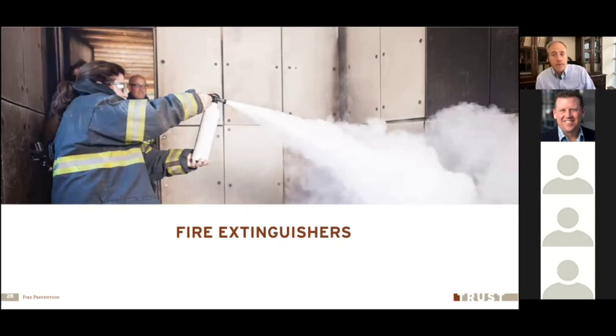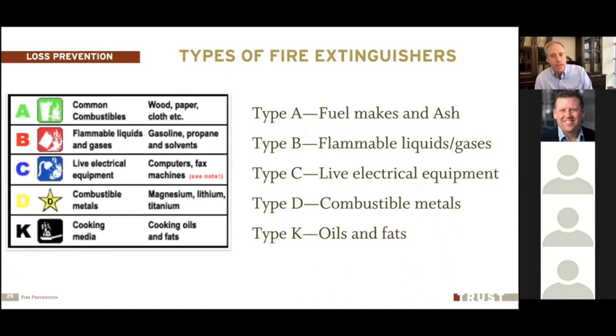And just take a second and talk about fire extinguishers. It's not fire prevention. We're going to use a fire extinguisher when there is a fire, but we should understand our fire extinguishers. There's basically 5 flavors of fire extinguishers. A, B, C, D, and K are the common ones that we see. Usually your fire extinguisher is going to be an ABC fire extinguisher. In other words, it will work on wood, paper, cloth. Also, it will work on flammable liquids and gases, and it will work on live electrical equipment as well. If you have a fire extinguisher that only identifies itself as A or as B or as C, be aware of that. It's only for the one. If you want to have a fire extinguisher that can handle all of these types of fires, you need to make sure you have an ABC fire extinguisher.